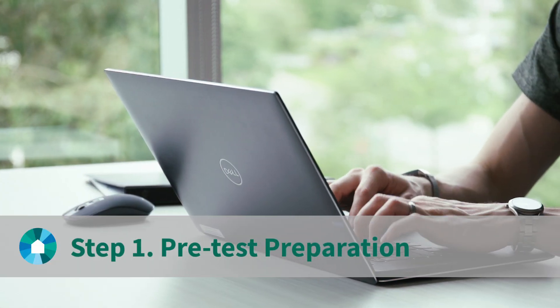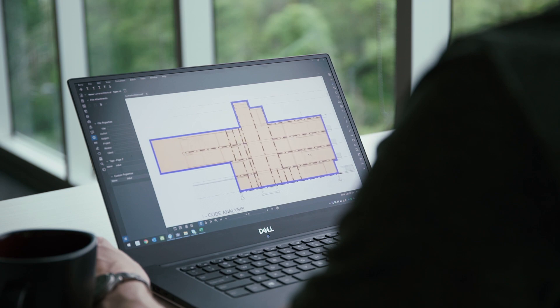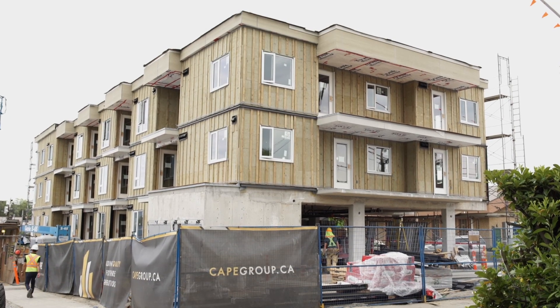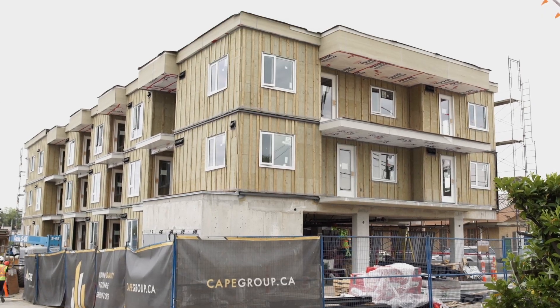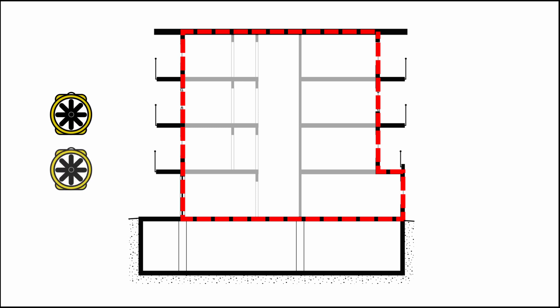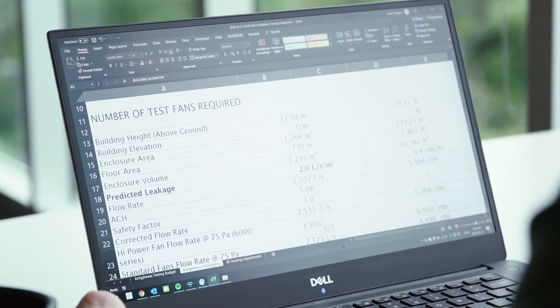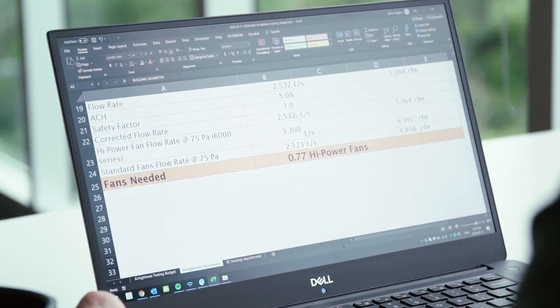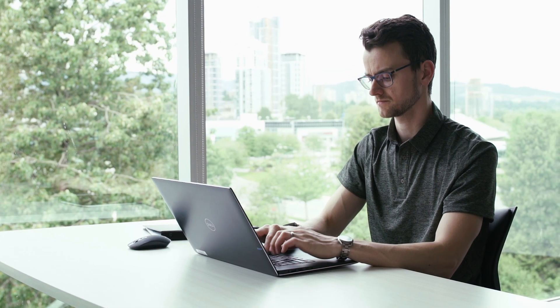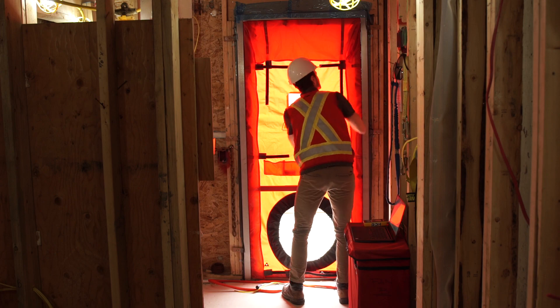A whole building air tightness test requires careful planning and preparation. It is important to confirm if the whole building can be tested at once as one zone or if it must be separated into multiple zones. Most mid-rise buildings can be tested as one zone, excluding the parkade. The building enclosure surface area is measured from the drawings and used to estimate the number of blower fans needed. The number of fans is determined by calculating the potential total airflow based on the maximum building air leakage rate and the maximum airflow that the test fans can provide. This planning work will help the tester and the team on-site understand the site preparation needed, including space allocation and power supply.